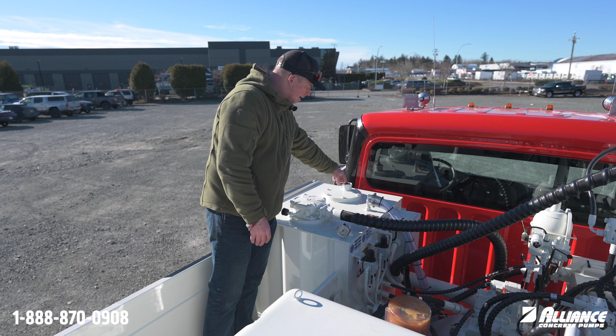But tank pressure gauge, this is your return filter. So every 500 pumping hours, we want to change this filter. You can access this filter from the top. There's a filter indicator gauge. It's a good thing to have a review on, because potentially before 500 hours you might have to change that if this gauge does go into the red. So there's an indicator there, it goes green to red.